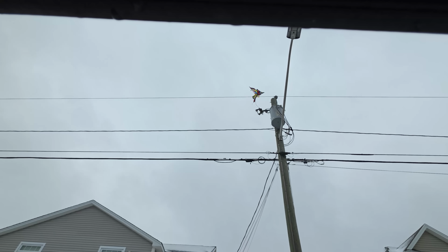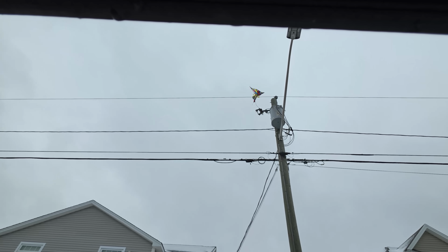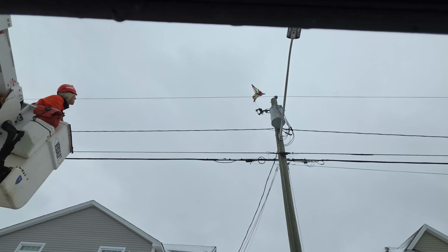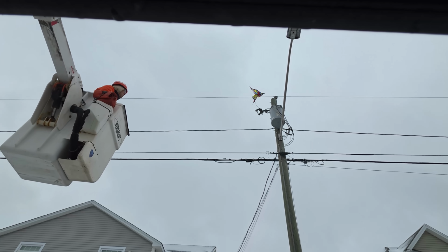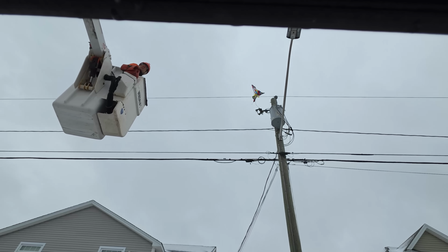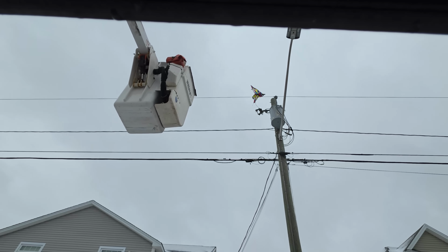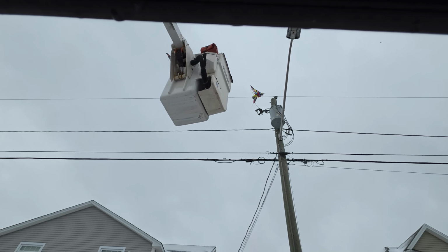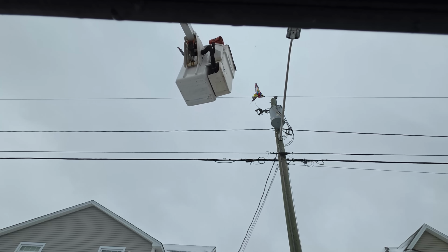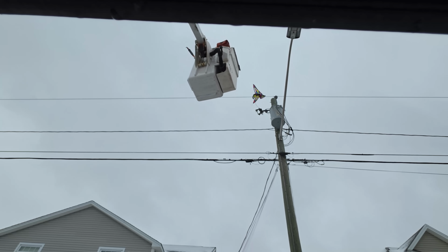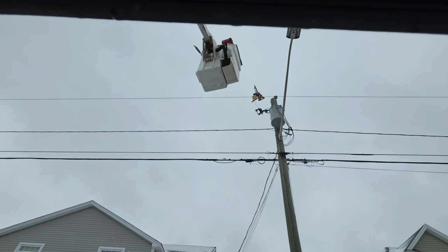With this kind of weather, especially with the rain, there's a constant kind of freezing fog in the air. That string is absorbing that moisture. It's a very real possibility that voltage could track through that string to ground. That being said, my first step when going up in the air, for those that are not linemen watching this video, I'm decked out head to toe in arc rated gear. Safety glasses, hard hat, multiple layers of arc flash gear in the event of a flash. So my first step, I'm going to use a hot stick. It's insulated for 100,000 volts per foot, as well as 20,000 volt rubber gloves, and I'm going to clear that string.